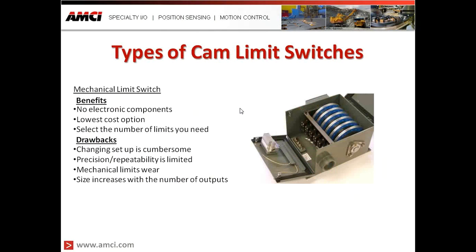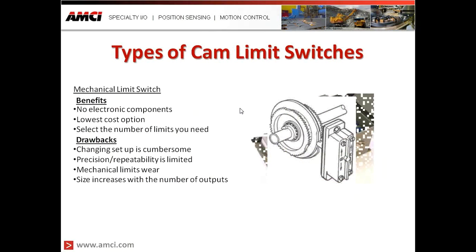The first type is a mechanical limit switch. The benefits are that there are no electronic components, making them very simple to use and a low-cost option. With a mechanical limit switch you select the number of limits you need — if you only need five, you order five; if you need twelve, you order twelve. As you can see in the picture, it's a simple concept: a wheel with a lobe that turns a switch on and off based upon the rotating shaft.